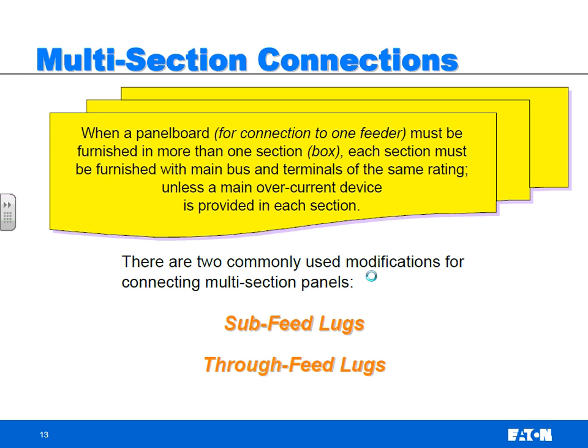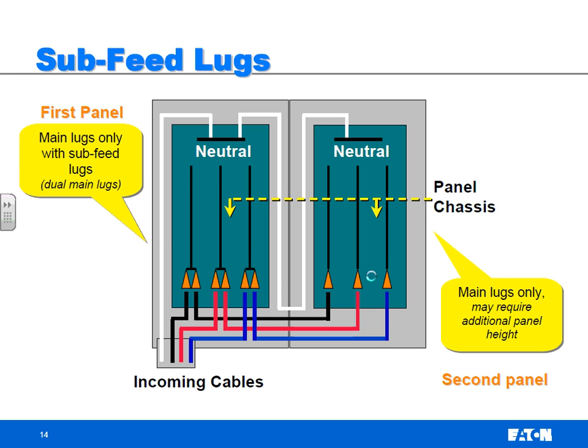So today, the only limitation on how many circuits I can put in a panelboard is physical space. Literally, can it all fit in there, or do I need another panelboard? Whether it's for code or I just like to keep my panelboard small, if I put 84 circuits in one panelboard, you're going to have bundles of wires coming out the sides, and it may get too cumbersome for someone's preference. So if I have 84 circuits and want to do it side by side, panelboard next to panelboard, the two options are sub-feed lugs or through-feed lugs. As straightforward as this concept is, it's one of the least understood, and you get a lot of questions. What's the difference? The difference is the power flow.